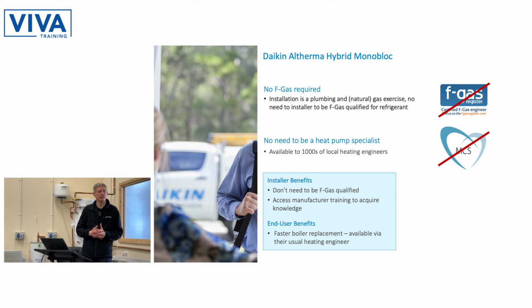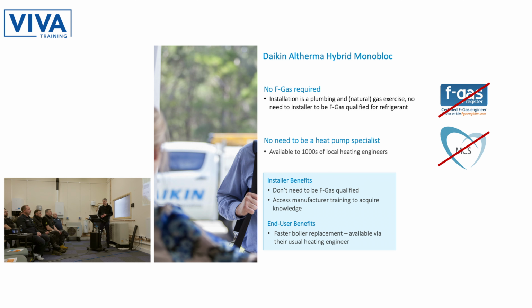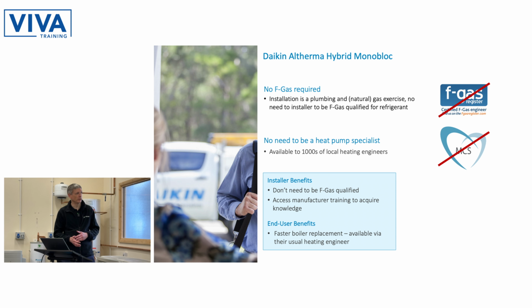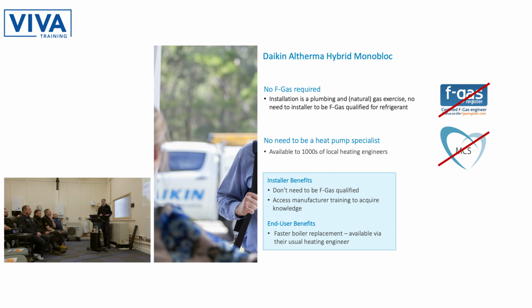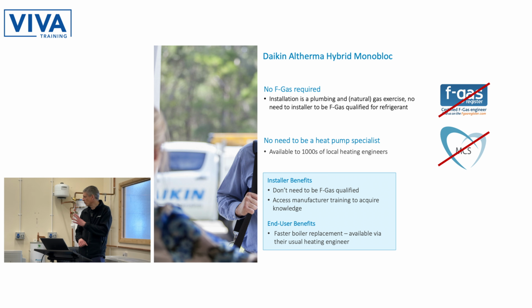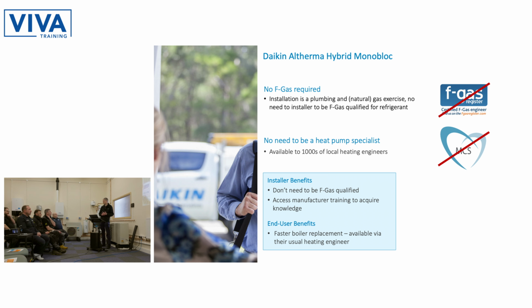I mentioned you don't need F-gas, so this is purely a plumbing exercise. If you can install a boiler, you can install one of these heat pumps. There's no funding for the UK, though there is funding for Scotland. Assuming none of you are working in Scotland, there's no funding available for this. But we've looked at this: if people need to upgrade their insulation, upgrade radiators, or put in a hot water tank, one of these hybrid installations can still be cheaper than a BUS-funded monoblock heat pump system, and quicker. So it's not necessarily.